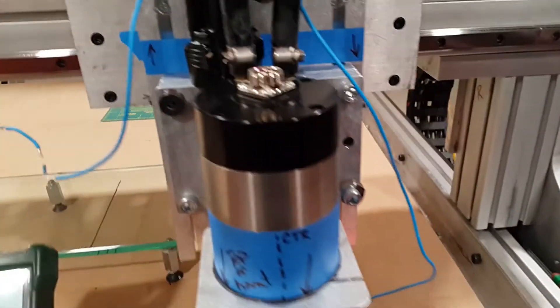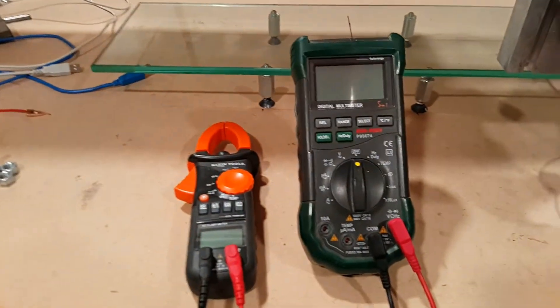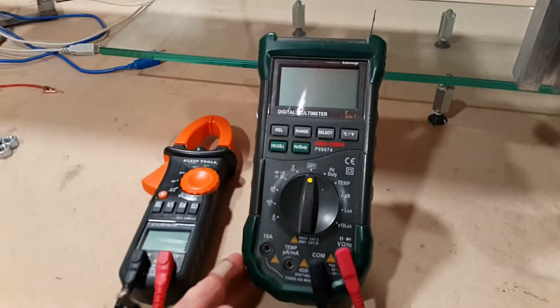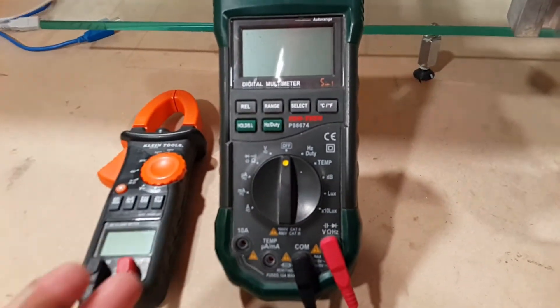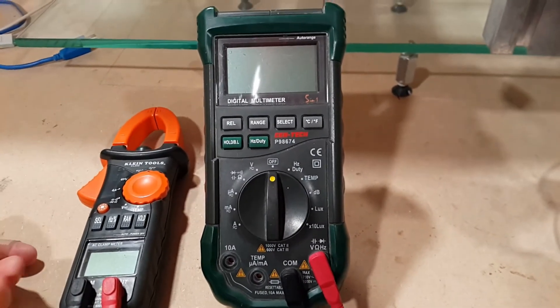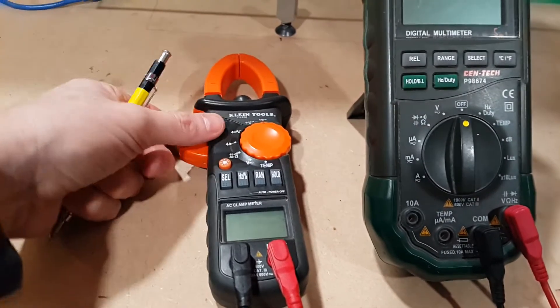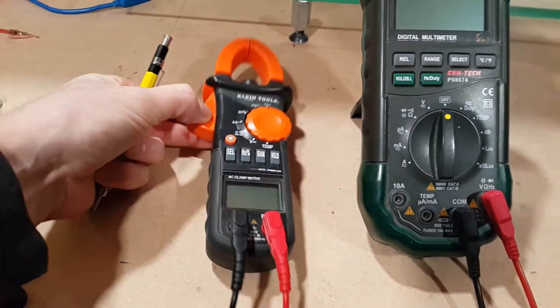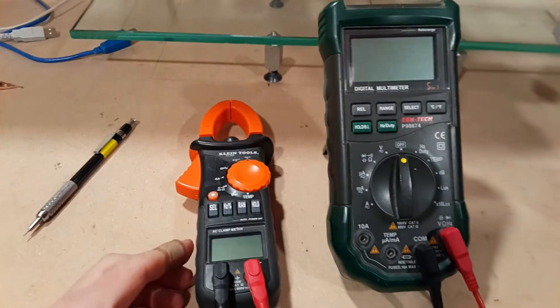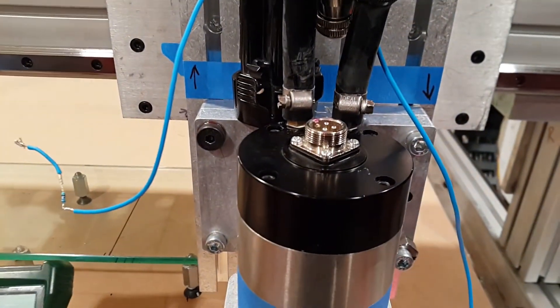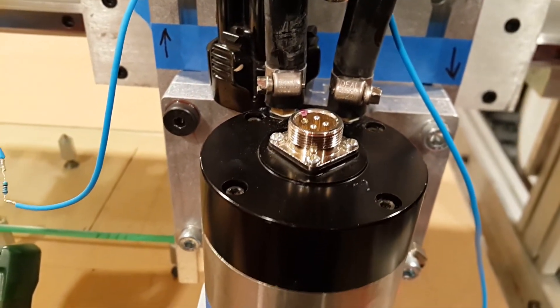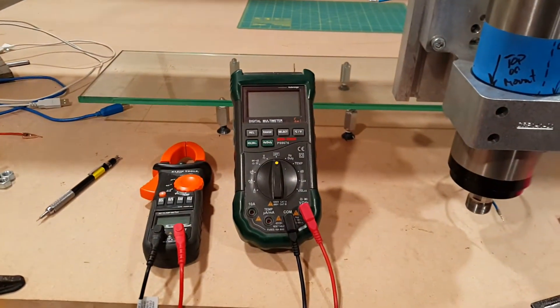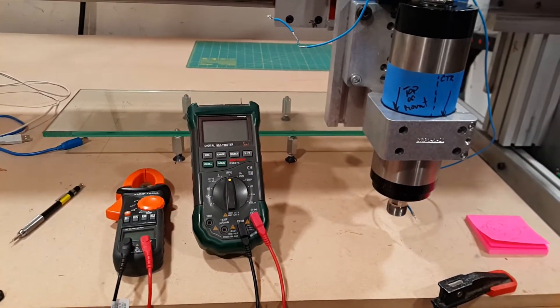So we're going to try to measure it, and these are the tools. You can start laughing now. This is the classic Harbor Freight multimeter. I actually like it, but it's not a true RMS meter at all. And then this is sort of a backup, also another probably quasi-junk meter, but these are the meters I have. We're going to do a four-wire measurement to try to measure the theoretically quite low value of resistance in each of the windings, so we can at least enter a number into the VFD configuration that's somewhat close. Let's get started.